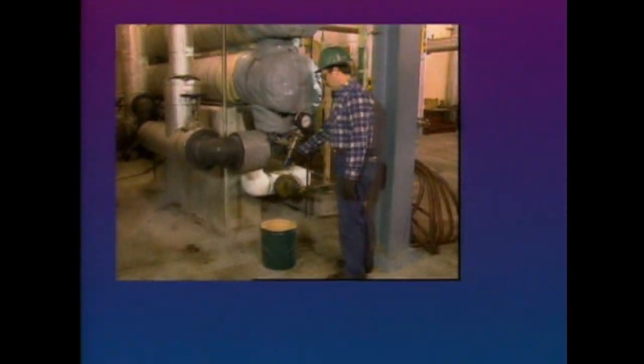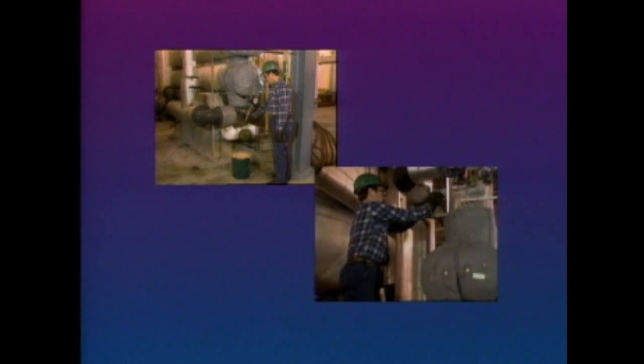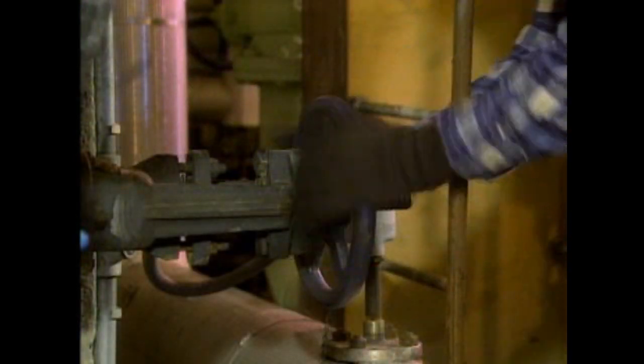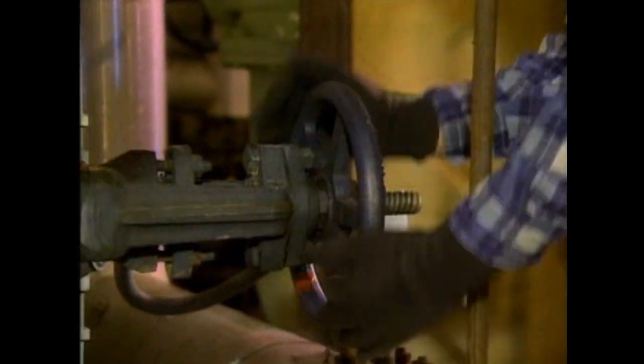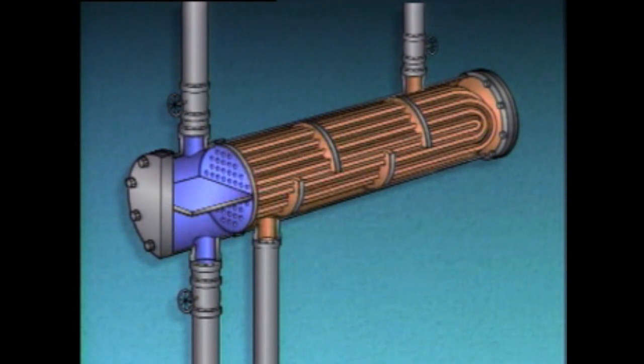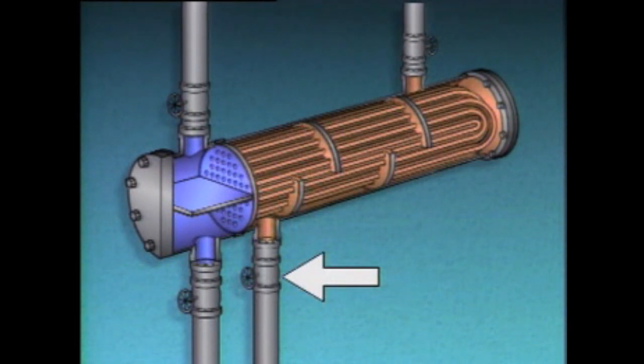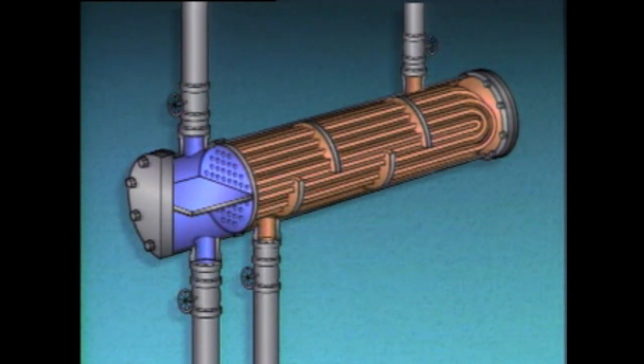When the tube side has cooled, the operator opens the tube side drain and vent valves. This allows air to enter the tube side and drains the process fluid. The operator then shuts the shell side inlet valve. On the heat exchanger shown in this example, the shell side has no isolation valve on its outlet. Some shell and tube heat exchangers have an isolation valve on this outlet; with those heat exchangers, the isolation valve must be shut to completely isolate the heat exchanger.